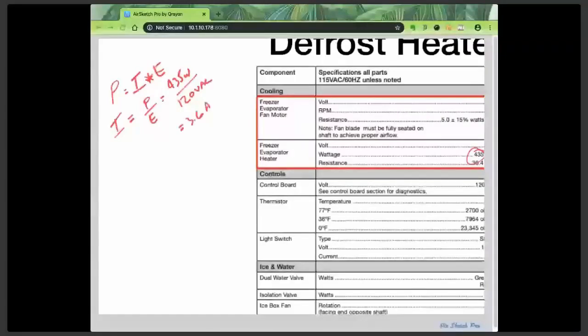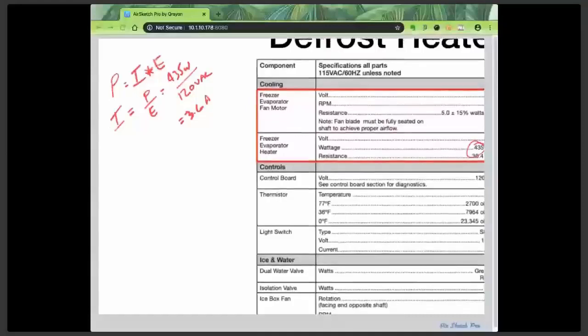So that's my expected reading if I'm testing that load under load, I'm testing that entire circuit under load. Now if I apply the tolerance, plus or minus 5%, to what we just calculated, 3.6 amps, I'm allowed a variance anywhere from 3.4 to 3.8 amps. So if I put my amp clamp around the wire going to my load of interest, and measure anywhere from 3.4 to 3.8 amps, I'm in spec.